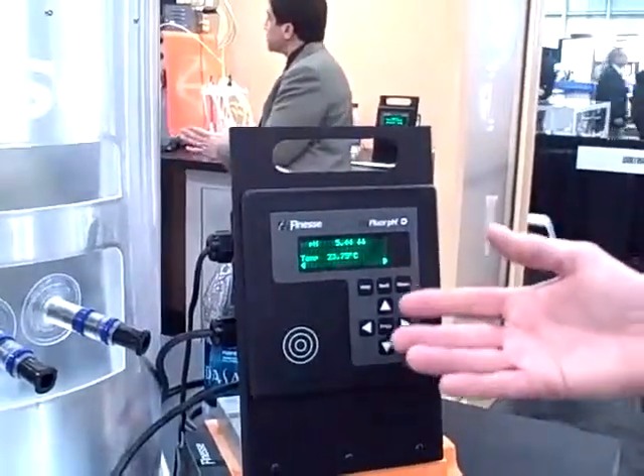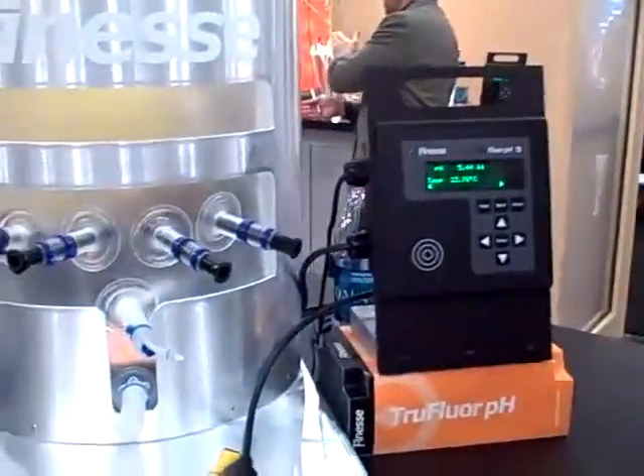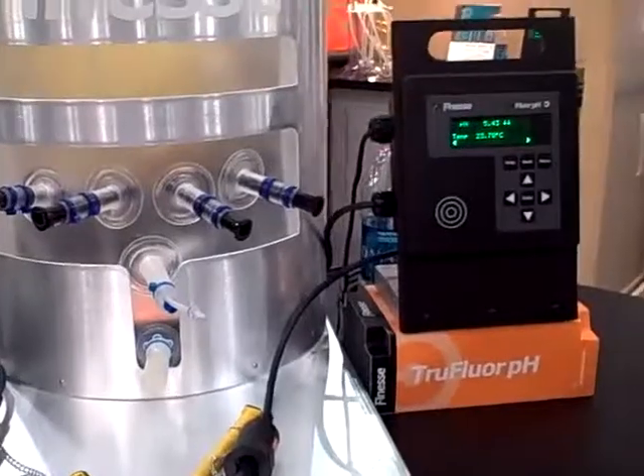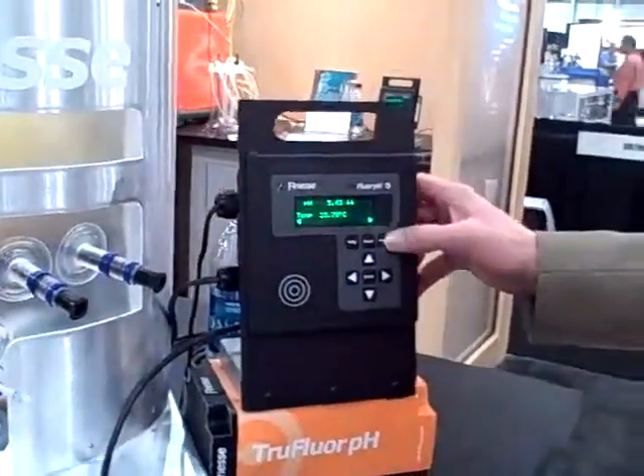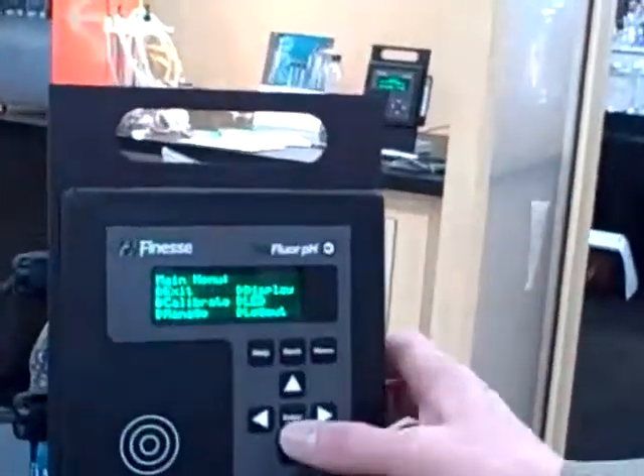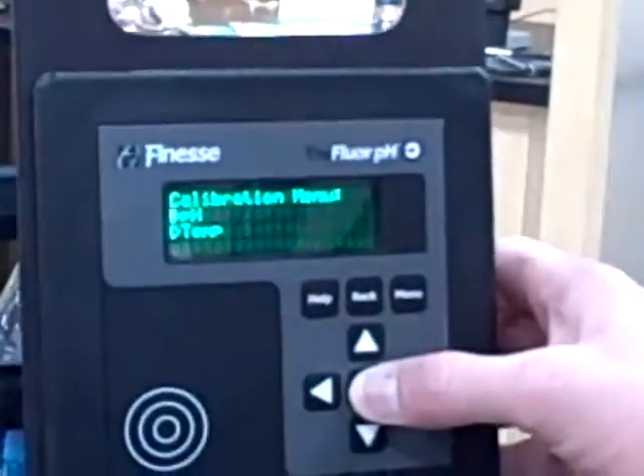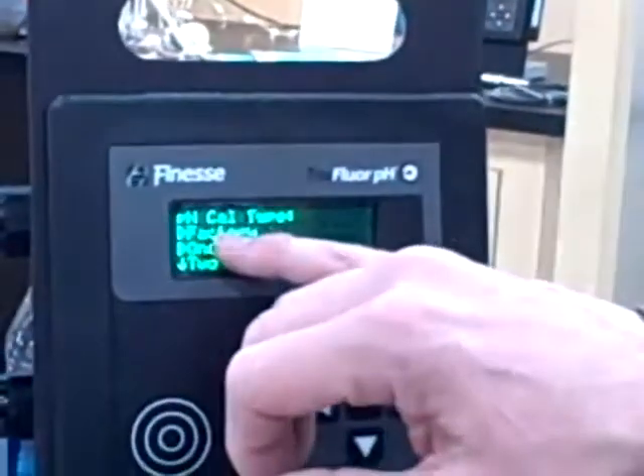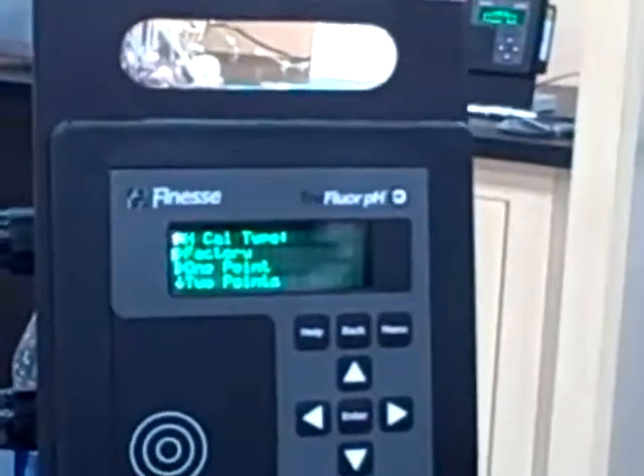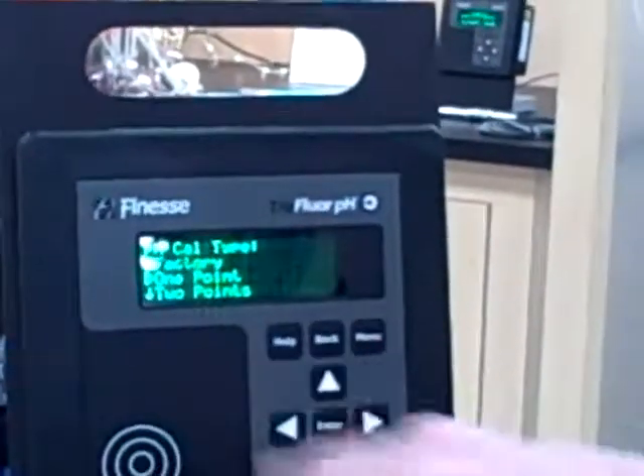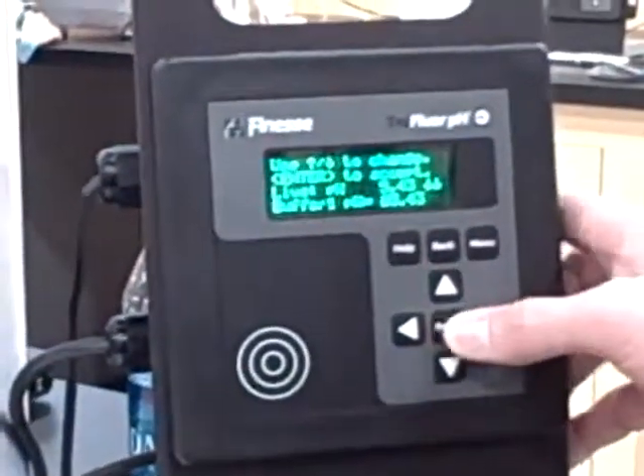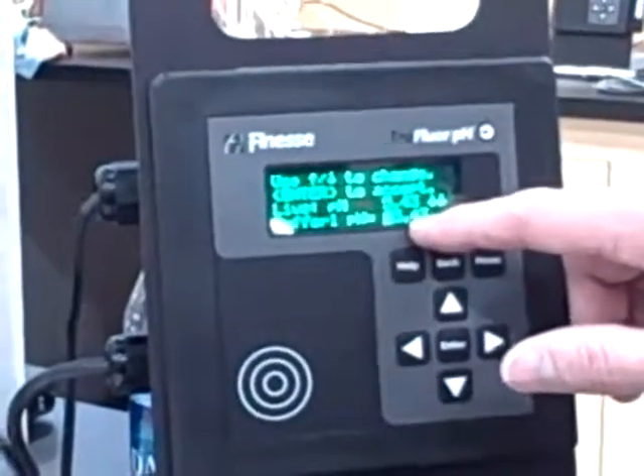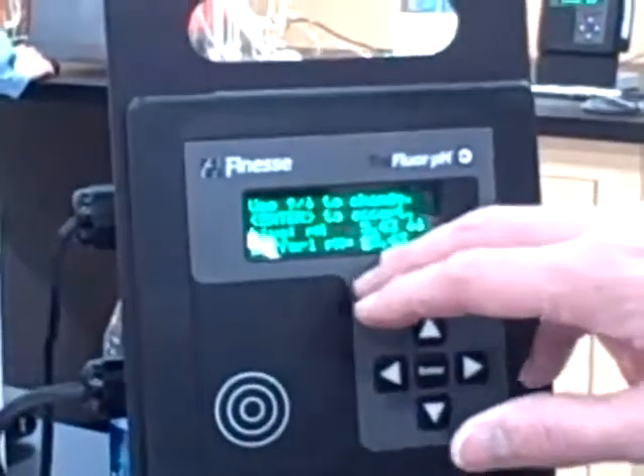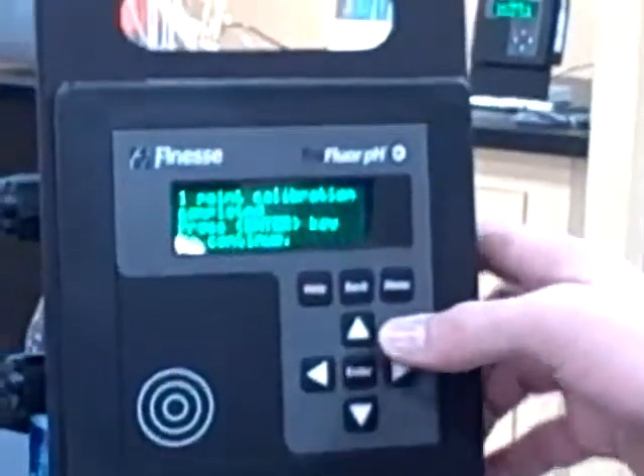With the pH, we recommend that you soak the sheath for 4 to 6 hours. Actually, you have to soak it for 4 to 6 hours before you do a calibration. Then you do a 1-point calibration and you're ready to go. Doing the 1-point calibration is simple. You press menu, scroll down to calibrate, pH or temperature. In this case, we're doing pH, and you can use a factory calibration, which would be the calibration in the sheath itself, or you can do a 1-point or a 2-point calibration. But as I mentioned, we recommend doing a 1-point calibration for accuracy. So you just press 1-point calibration, then you come down here, take your offline reading and translate that here, press enter, and then you're ready to go.